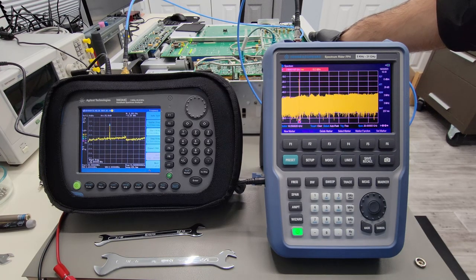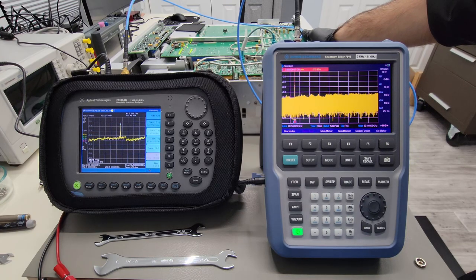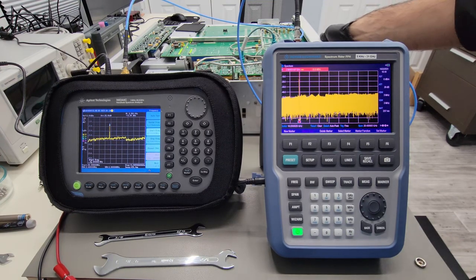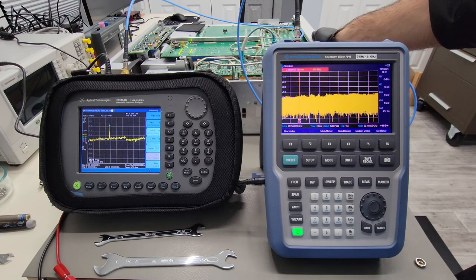I don't see any problems with the couplers or the amplifiers for those coupled signals that are inside of the 20 gigahertz doubler microcircuit. If those were an issue, that would be a pretty difficult repair because that's all wire bonded. And it's not on the PCB itself, it's inside of this machined microcircuit cavity inside of that assembly. So it's a good thing that those are working. And the amplitudes look correct as well.